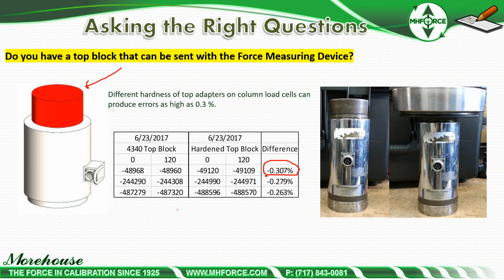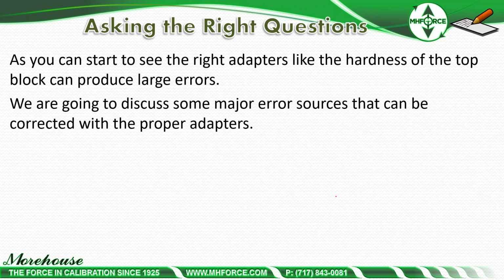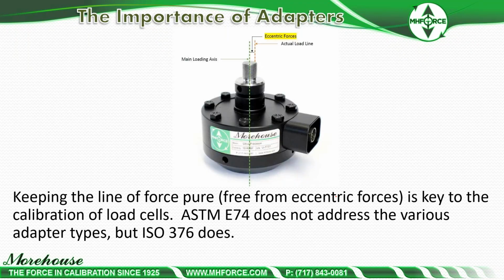What was the expectation? The expectation is better than 0.025% at capacity. So we are more than 10 times out of the expectation just from switching top blocks. As you can start to see, the right adapters, like the hardness of the top block, can produce large errors. We're going to discuss some major error sources that can be corrected with proper adapters. Really, calibration is all about keeping the line of force pure, free from eccentric forces. ASTM doesn't address it. ISO 376 appendix does.